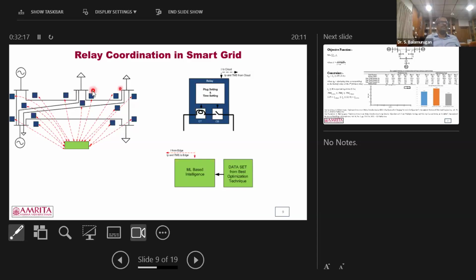So coming back to this, whatever blue color you are seeing here, the same blue color is what is given here. Only thing is this is a small edge control. In this edge control, the small component we have is the IEC characteristics, which is available in this particular relay. All the power system information is already available in the cloud. So the cloud will decide what the TMS value and the plug setting value should be, that is the plug setting and time setting of this relay for that IEC characteristics. That will be decided in the cloud, and only the TMS information and the plug setting information will come from the cloud to this particular edge. So now this relay is capable of working on the characteristics as you expect.